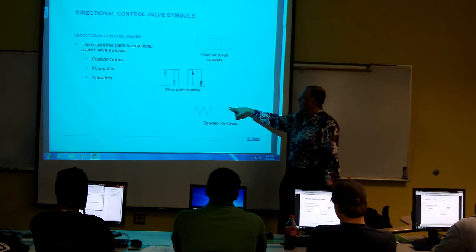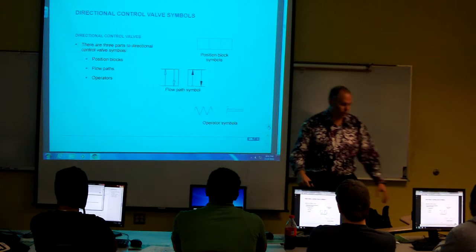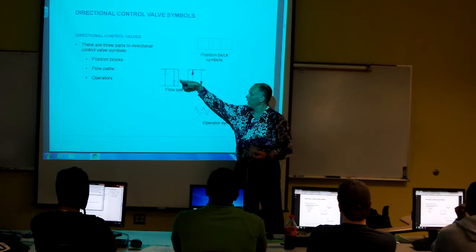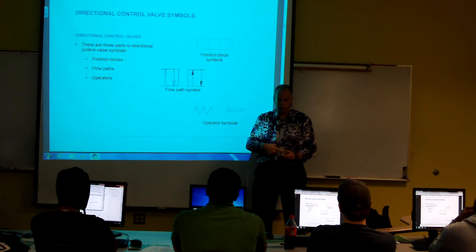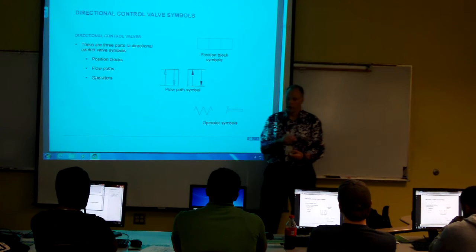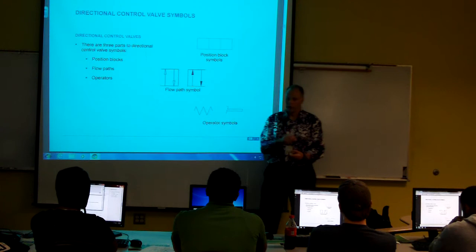Operator symbols. How are you moving between the positions? In this case here, this is a tube. This would be a tube block, and it will just have arrows in and out in each direction, and it's manually moved. If I push it this way, fluid would come through this one and go out this one. If I push it this way, fluid would come in and go out that one. It's all it is. It's a manually controlled valve, and in this case here, it may look like something like a lever. This would be a lever.